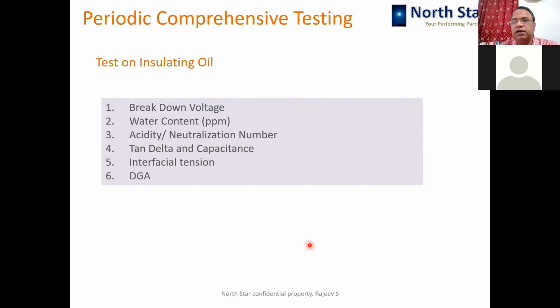So DGA basically tells you about various factors, including the condition of the contacts. It is telling you whether some arcing is happening or not. It is telling you the insulation is decaying fast. It is telling you where some hotspot is getting towards a severe situation, whether the transformer is giving some other kind of problems, whether the gas is generating because of your insulation moisture, whether the moisture is very high. So all these things you can find out by doing DGA. So DGA is done not as an oil test, but it should be done as a transformer analysis test.